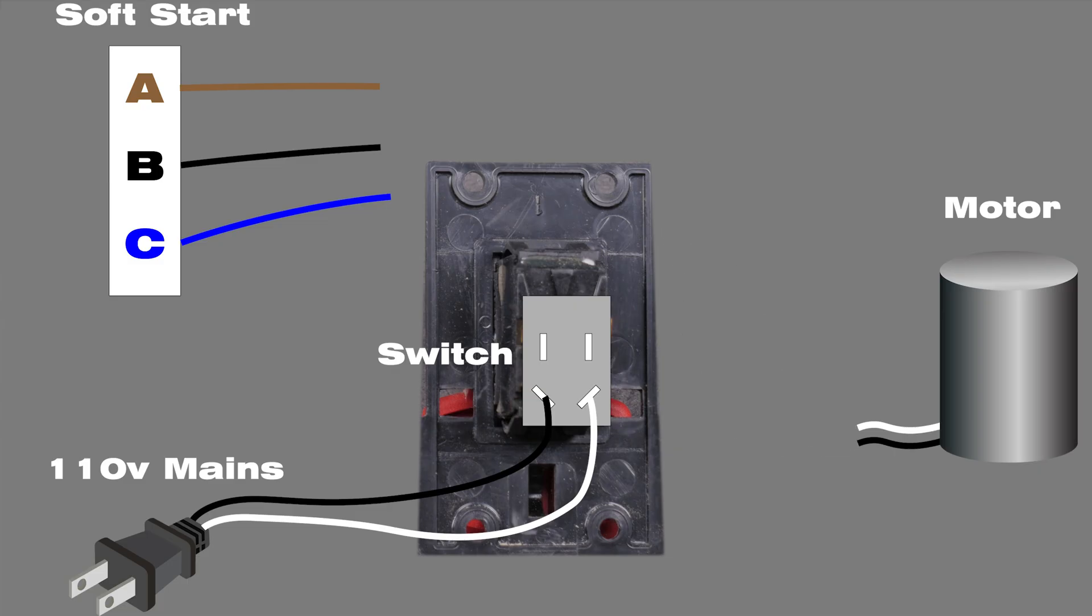The brown lead connects to the switch pole opposite the mains hot or black wire. The black lead connects directly to the hot or black lead on the motor. The blue lead connects to both the switch lug opposite mains neutral as well as the white neutral motor lead.